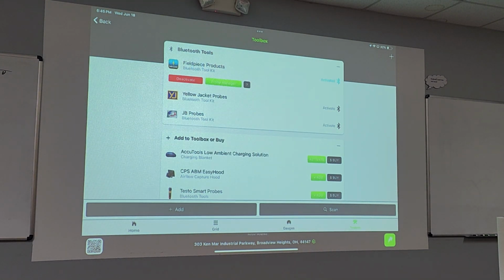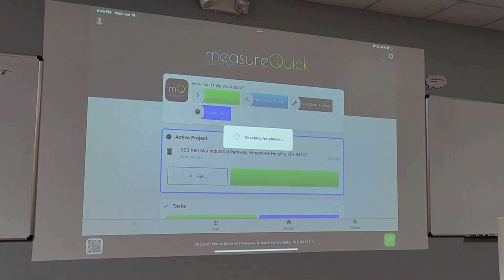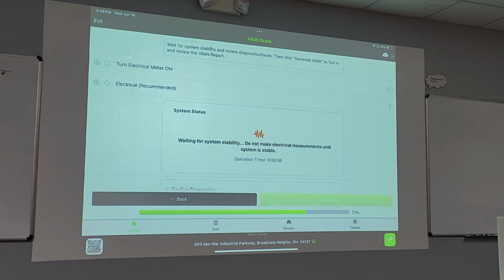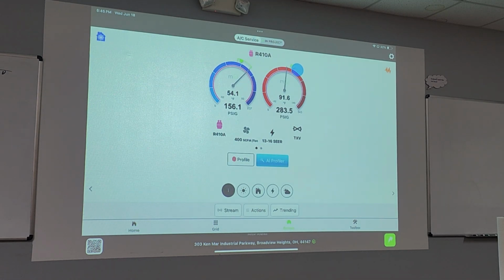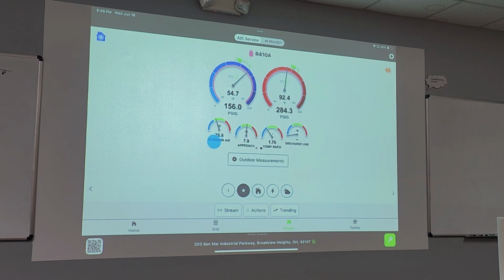No, it is just a little honesty check, so that if you're manipulating your outdoor air temperature probe to change your head pressure target, this target right here for your head pressure is driven directly off of your outdoor air temperature probe. So theoretically, if you had a dirty condenser and you didn't want to clean it, you could heat the outdoor air probe up a little bit to drive the head pressure target up a little bit and make it look like everything's okay. But then on the report, you'll see this measurement, and then you'll also see this. So if you see 82.7 out, and this is saying 100, whoever's reviewing the report will go, wait a minute.